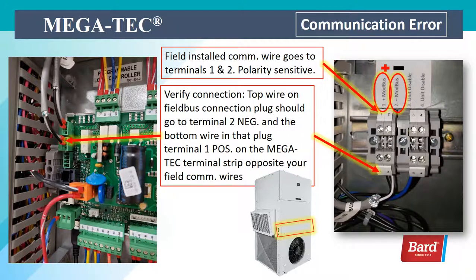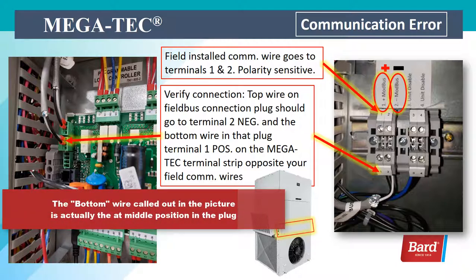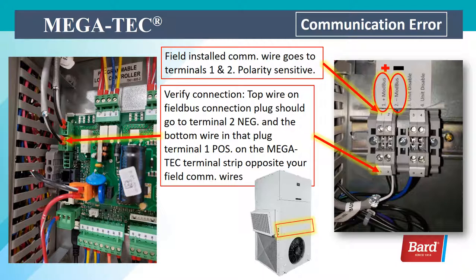If you're working with a Mega-Tec unit, the field-installed communication wire goes to terminals 1 and 2 as shown on the right, and these are polarity-sensitive. We need to verify the field bus connection inside the unit: the top wire on the field bus connection plug should go to terminal 2 (negative), and the bottom wire in that plug to terminal 1 (positive) on the Mega-Tec terminal strip — opposite your field communication wires. The arrow points down to terminals 1 and 2 where the PLC connects, and at the top of that terminal, 'positive mod bus' and 'negative mod bus' labels indicate where your field wiring connects.